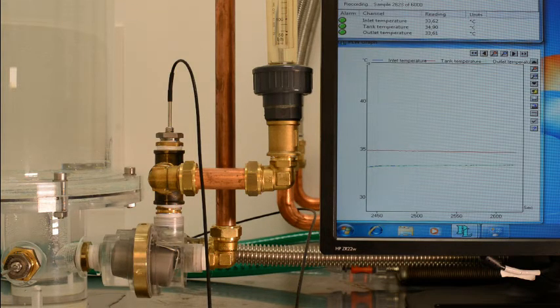So now we're looking at the setup a bit more close-up to get an even better look at what's going on, and we'll do the experiment a bit slower, heating up slower and cooling slower, so we can see very well how accurate the valve is when in its switching position. So we're starting again with the valve being in the bypass position, because the inlet temperature is lower than the tank temperature, and you will see because then the blue and the green line are below the red line and they are fully overlapping. So the valves both are at 33.64, so it's 100% closure, even though the temperature is only just over a degree below the tank temperature.